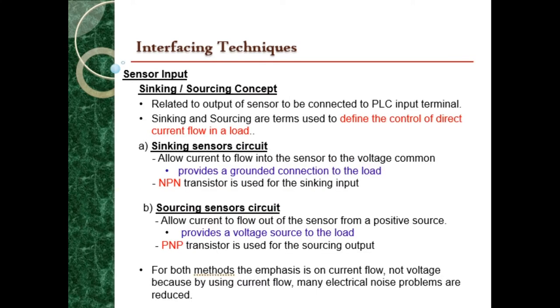After we have ensured the connection between the power source and the PLC, we need to look into the concept of sinking and sourcing in the interfacing techniques between the sensor input and the PLC. The sinking and sourcing concept is a normal term that is used to define the control of direct current flow in a load.